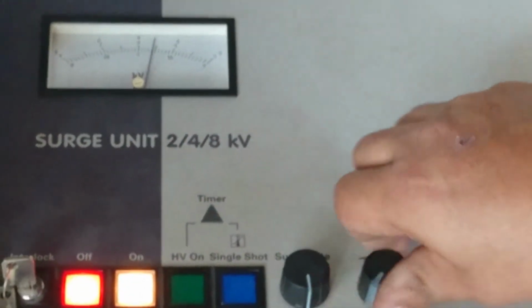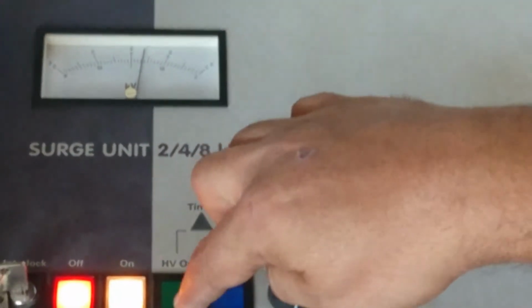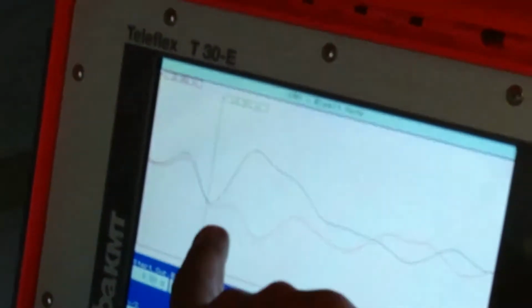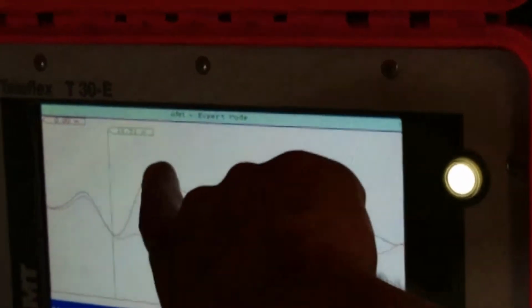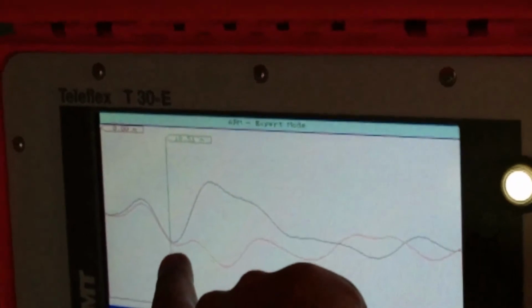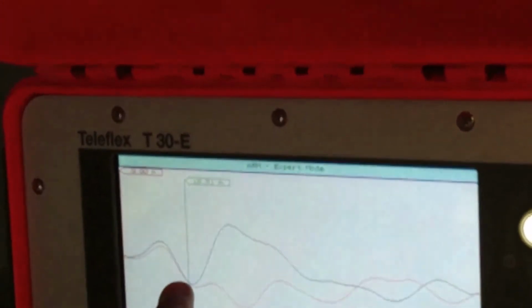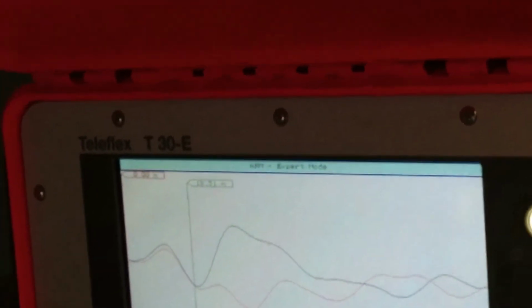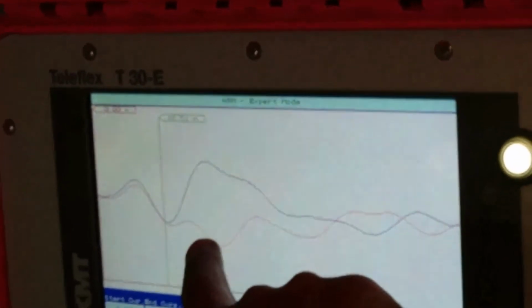I can remove the voltage, and I gave a single shot. This is waiting for trigger, single shot. When I get a single shot over there, a flashover happens on that faulty area, and then I have 2 traces, the same as what I did manually, but it does it automatically. I have the open end, and after the flashover, automatically it picks up where the fault is. So this is the faulty area where it changes over between reference trace and faulty trace, we call it reference trace, faulty trace.